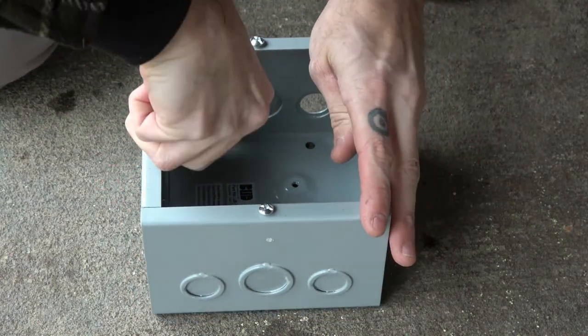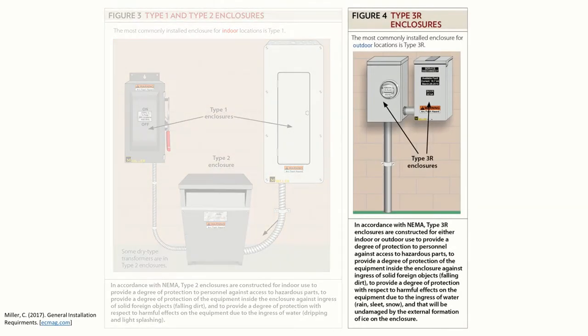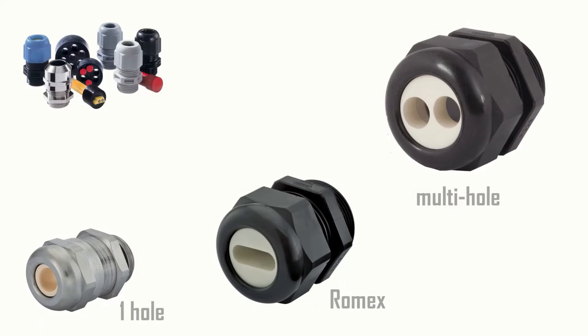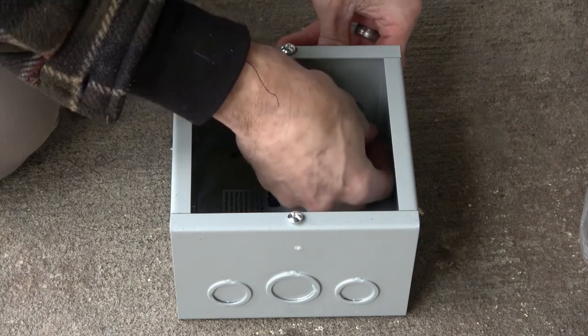It was just the only option that I had readily available at the time this video was recorded, but hopefully in the least it demonstrates the essential components and connections that are needed. Again, you'd actually need a NEMA 3 or NEMA 4 rated box whenever you're installing outdoors or in a wet location, but just for demonstration, we're going to put the various wires that we have today into this enclosure. And we'll need to use wire strain release in general to ensure a watertight passage for each type of wire. While something like a Romex connector is designed for indoor use only, we're going to use two-hole waterproof strain release in this video for all of the PV cable.